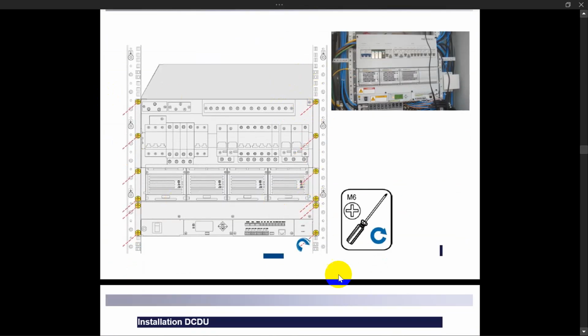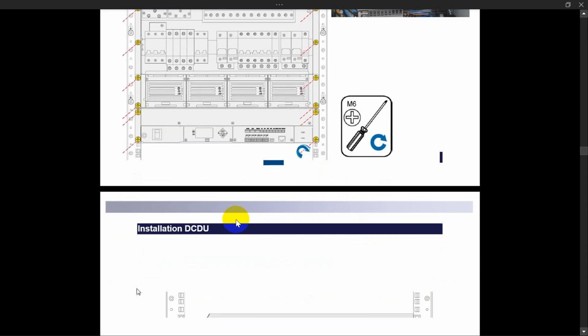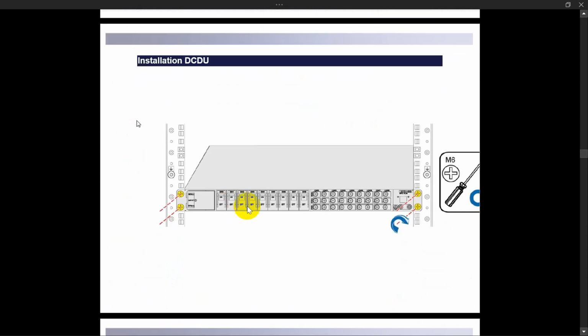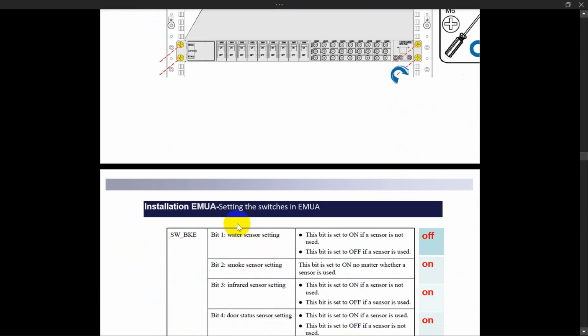This is how we are fixing the rectifier. We must use the 19-inch rack, and for this rectifier we have more screws on each side, and all must be fully tightened with M6. We will fix both ends with 6 screws. Same for the DCDU, and it will also be the same for the EMU.